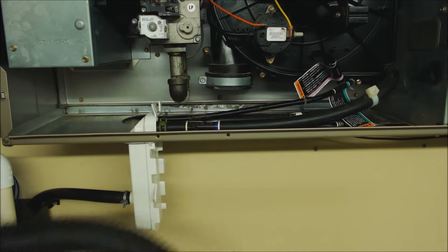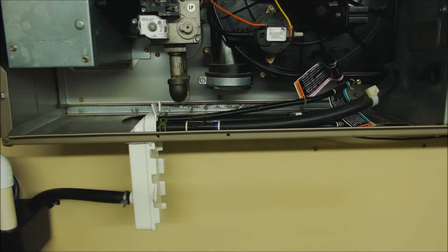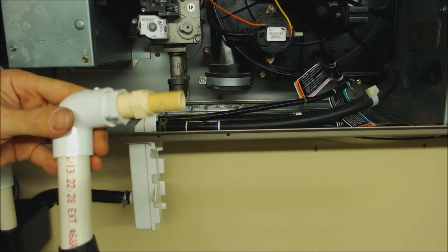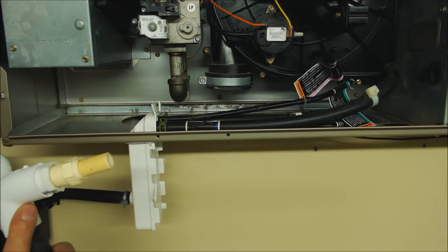Now if you're going to vacuum it out it's going to be even simpler and we just use a two gallon shop vac. And on the end of the hose I just have some fittings made up in order to reduce down between three quarter and then half inch CPVC. A lot of these 90% efficient furnaces use sizes that are matched up to half inch CPVC.